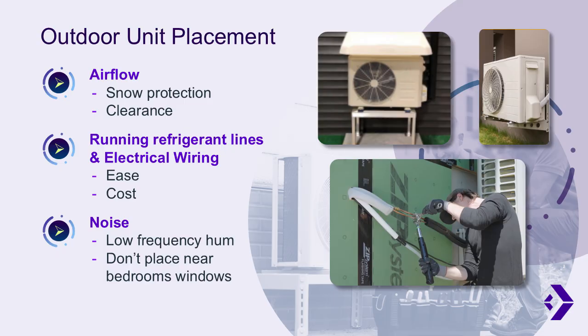Second, snow protection. Ideally, you want the heat pump on the gable side of the home. The eave side is where snow typically sheds off the roof. A big roof dump can bury or damage an outdoor unit. The gable end avoids that snowdrop and provides protection, especially when combined with snow deflectors. If the unit must be installed on the eave side of the home, snow deflectors are especially important and should be installed. Additionally, remember to protect the heat pump from snow accumulation below. Ensure the unit is elevated above the average annual snow height to provide adequate clearance.